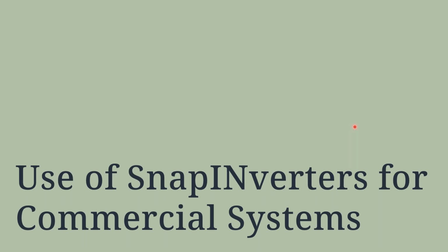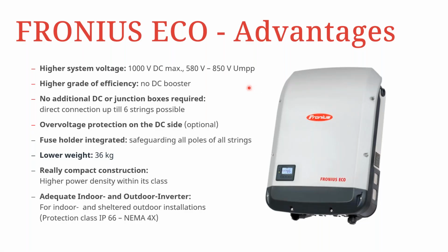So when it comes to the use of the Fronius Snap inverters in commercial systems, let's look at the advantages, for instance, of the Eco inverter. So the number one thing that you will note with the Fronius Snap inverter Echo is the high input voltage that we mentioned, 580 to a maximum of 850. That is at maximum power point. Of course, the open circuit voltage is limited to 1000 volts, and it has a higher grade of efficiency because the booster circuit within the inverter is missing, and therefore it means that you have to be quite careful when you are designing the string voltage for the Fronius Snap inverter Echo.